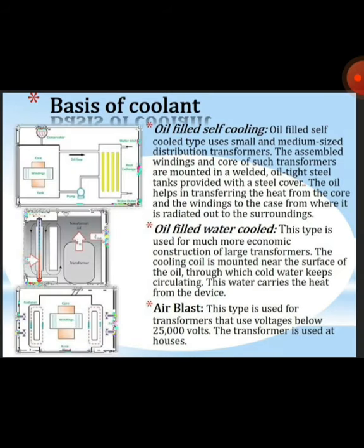On the basis of coolant, oil filled self cooling. Oil filled self cooling type is used for small and medium sized distribution transformers. Assembled windings and core of such a transformer are mounted in a welded oil tight steel tank provided with a steel cover. The oil helps in transferring the heat from the core and winding to the case, from where it is radiated out to the surrounding.